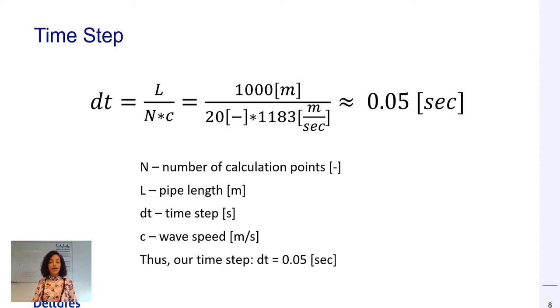It's important to note that the number of the calculation points n must be an integer to ensure that a number of elements of equal length fit in the total length of the pipe. Thus, Wanda automatically adapts the wave speed according to the chosen time step to ensure that n is an integer.